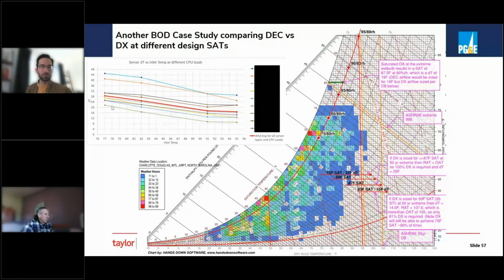There's a lot going on here. Let me try to unpack it quickly. This is a bin plot of all the hours in climate. We were looking at things like direct DX cooling, basically packaged rooftop units with DX, and airside economizing was one of the options. And so if we used, say, a 75 degree supply temperature, we would need a 25 degree delta T at the air handler. And we would need 100% DX cooling capacity because our return air would be below our extreme ambient dry bulb.